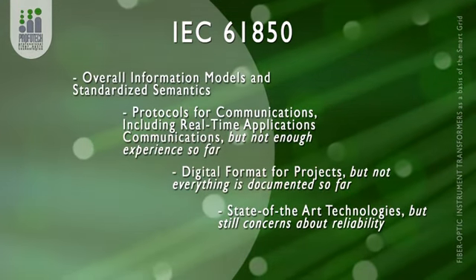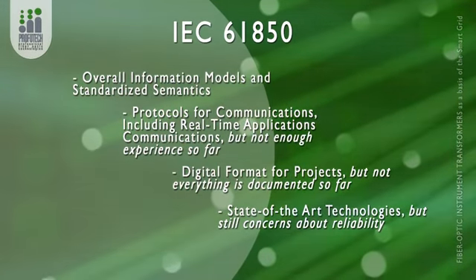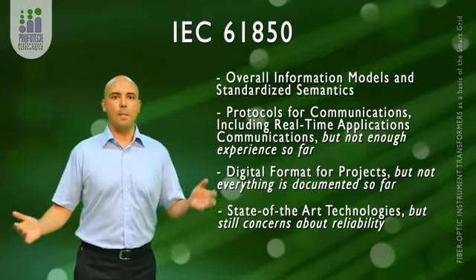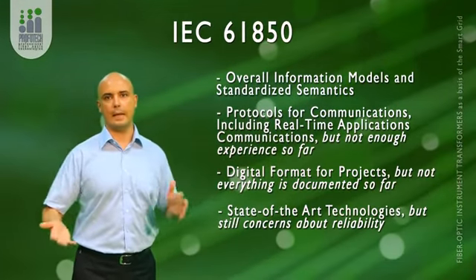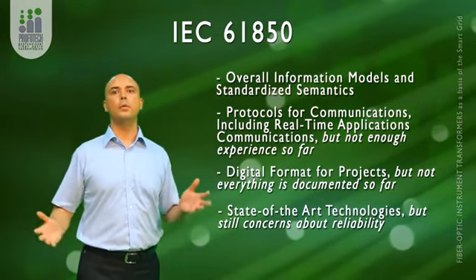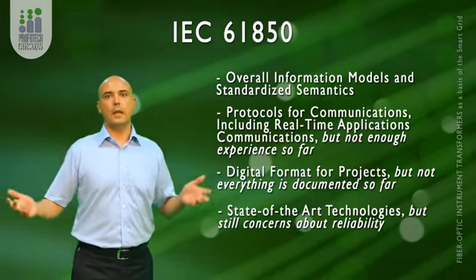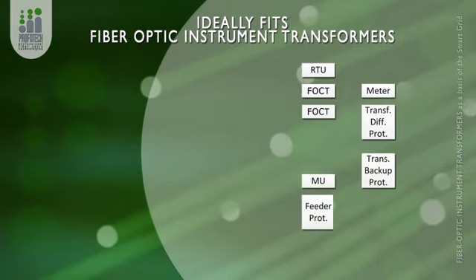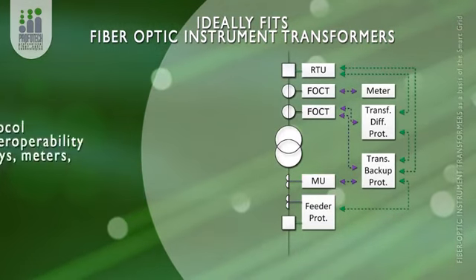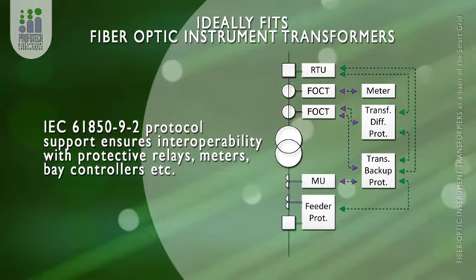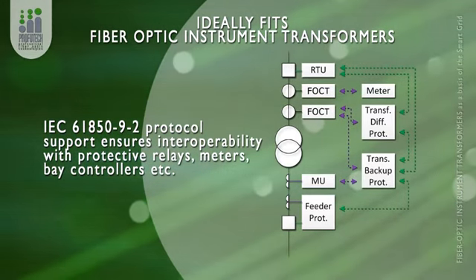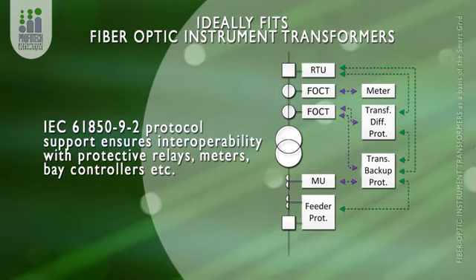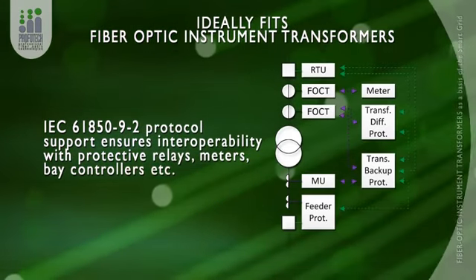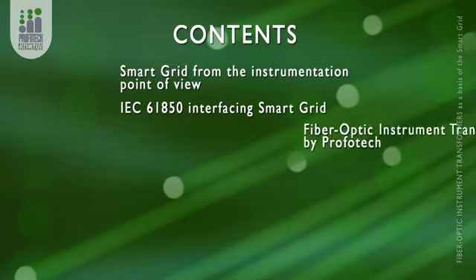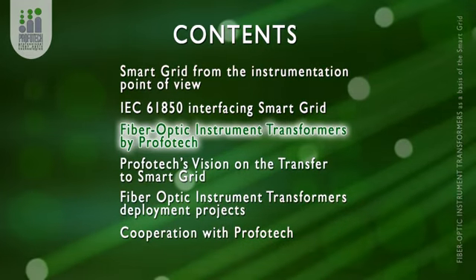However, the drawbacks of the IEC 61850 standard are associated with the fact that this standard is new and very complicated. In fact, at the moment, it has about 26 documents included in the standard, and they are pretty big. Another problem is those people who don't want to study this documentation. They just say that this standard is not mature enough. The protocol and standard IEC 61850-9-2 is ideally fit to introduce fiber optic instrument transformers and non-conventional instrument transformers for power energy as a whole, because it ensures interoperability of the instrument transformer with digital interface with other secondary devices like protection, metering, power quality, and so on. I would like to introduce you to the fiber optic instrument transformers developed and produced by Profotech company.